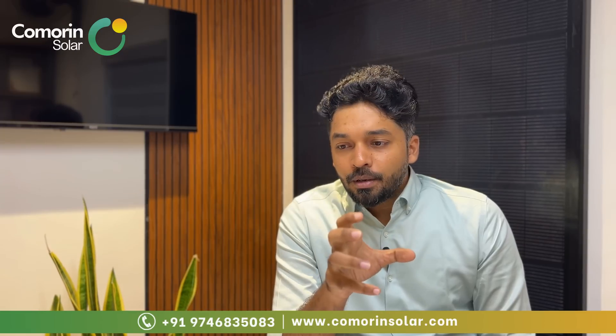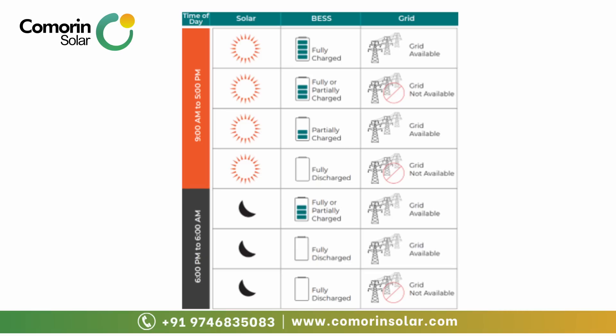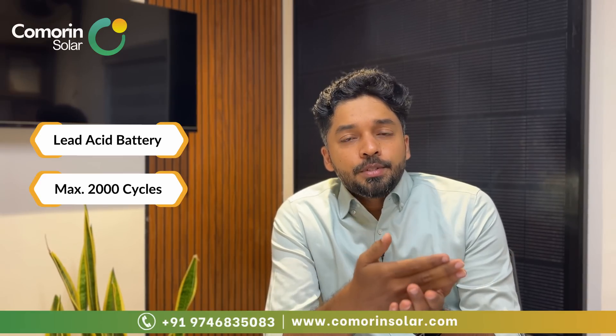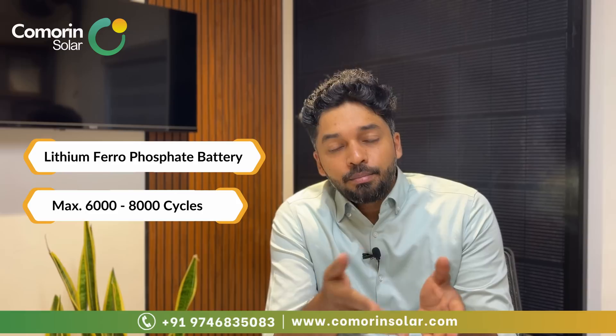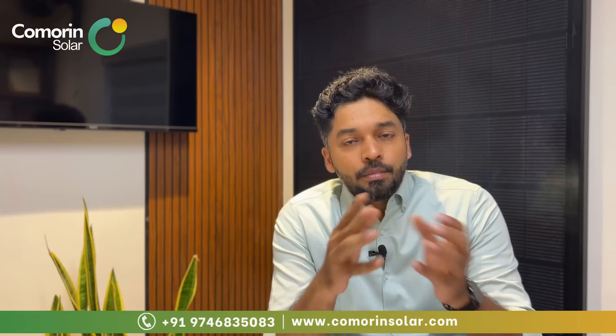To count a charging cycle, the battery must go from full charge to full discharge. Lead-acid batteries typically achieve a maximum of 2,000 cycles, while lithium batteries can achieve 6,000 cycles, and premium lithium batteries can offer up to 8,000 cycles. This makes direct comparison between lead-acid and lithium batteries quite challenging.